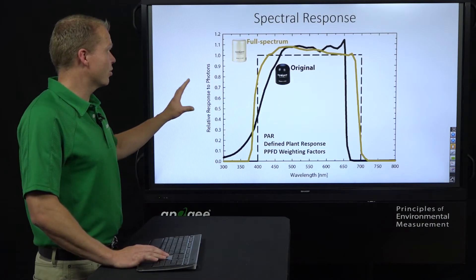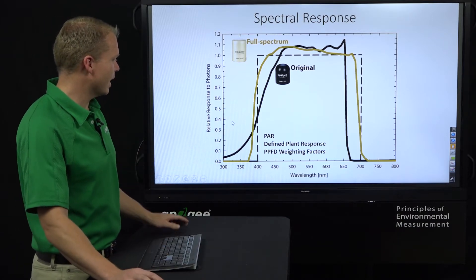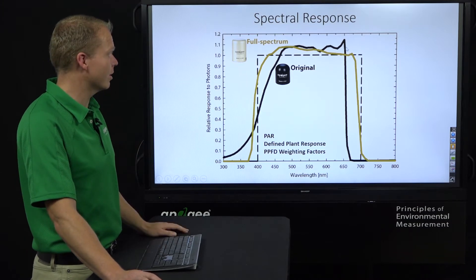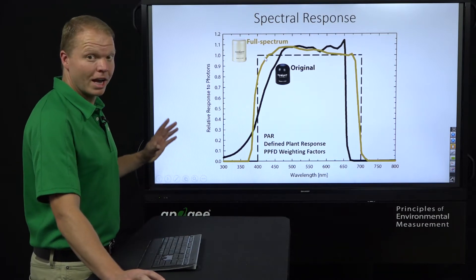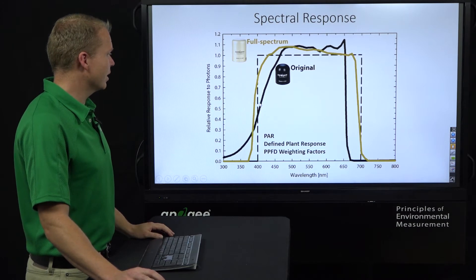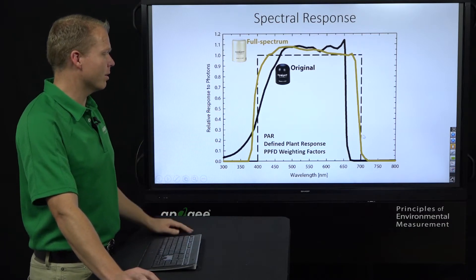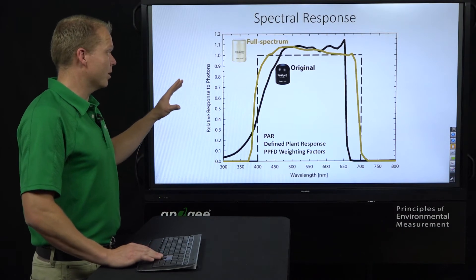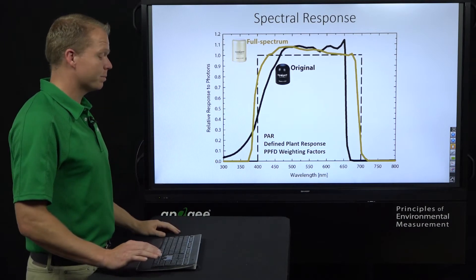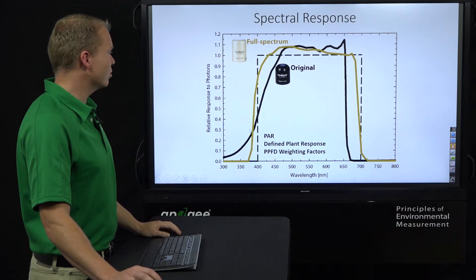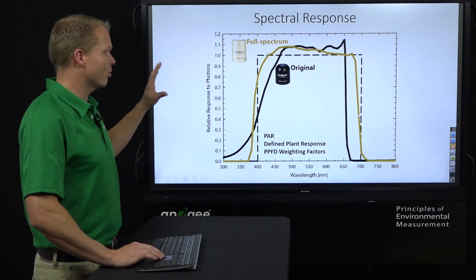Full spectrum versus original spectral response. We need to define PAR as how the plant sees light — that's the dashed line from 400 to 700 nanometers, which is ideally what a PAR sensor would match. Our original sensor cuts on a bit late, cuts out a little of the blue, and completely cuts off some of the far red above 665 nm. So we calibrate it for either sunlight or electric light sources. The full spectrum sensor more closely matches that PAR response and gives much more accurate readings for all light sources.